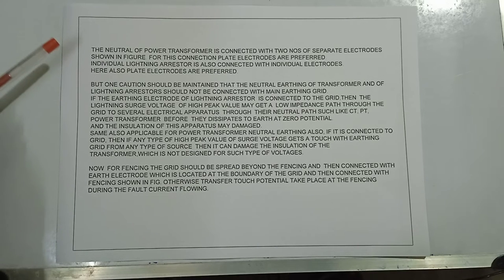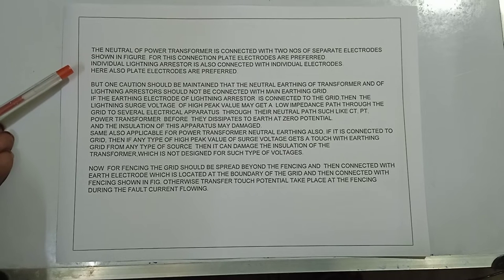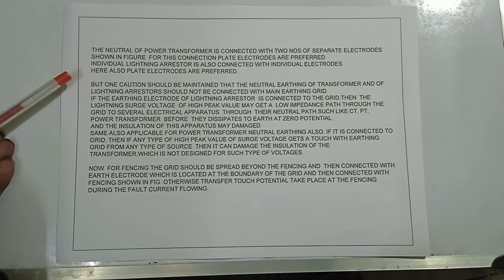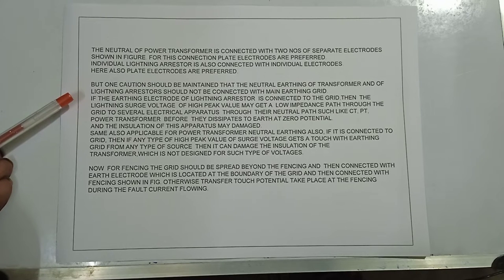The neutral of the power transformer is connected with two numbers of separate electrodes. For this connection, plate electrodes are preferred. Individual lightning arrestors are also connected with individual electrodes, and plate electrodes are preferred here as well. One important rule: the neutral earthing of the transformer and the lightning arrestors should not be connected with the main earthing grid.